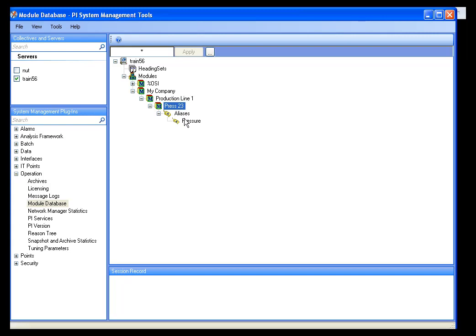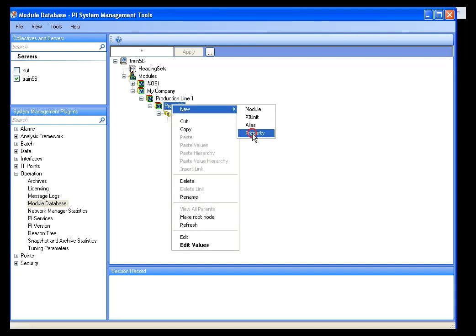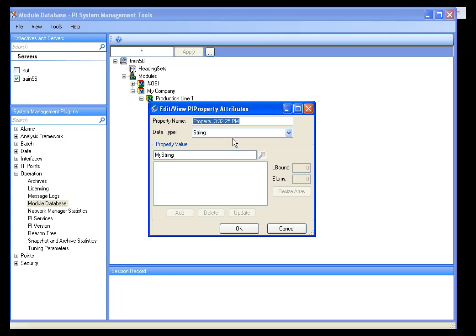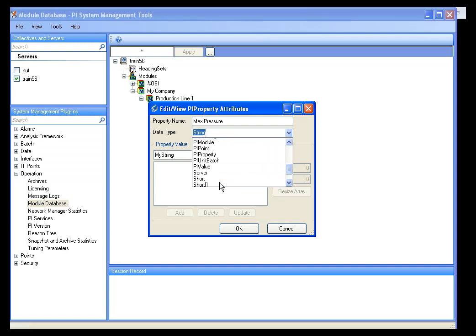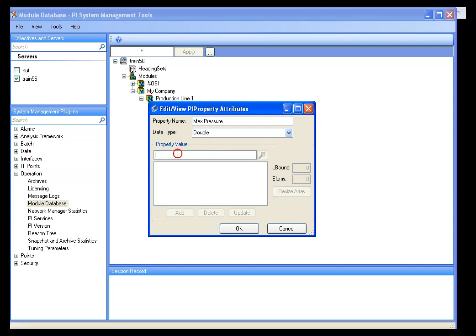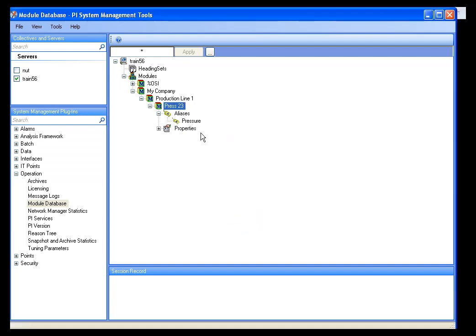This is just an example, so I do not have to tie a real tag to this. I will click OK, and you can see that we do in fact have an alias. I want to do the same thing for properties as well. I want to know what the target pressure is — what we will call the max pressure — and I want to store that as a property because I know what that value is. That is part of the specifications for the lines and the equipment. So I will call this property Max Pressure, and I am going to use a double data type with a value of 32.567. And I will click OK.